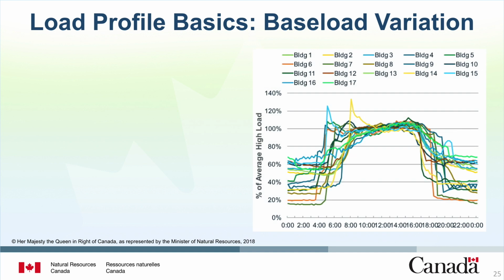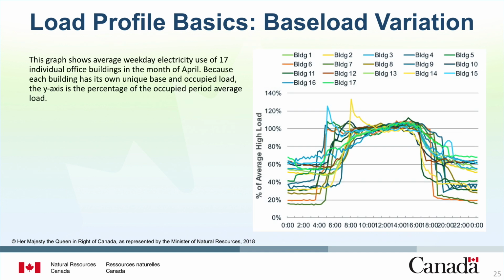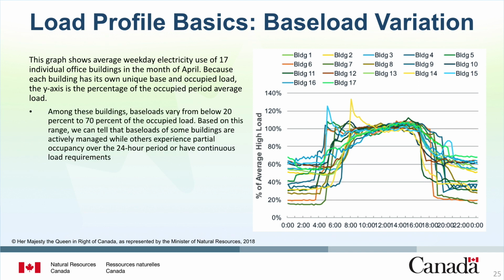We can also learn from load profiles that base loads can vary widely from building to building. This graph shows average weekday electricity use of 17 individual office buildings in the month of April. Because each building has its own unique base and occupied load, the y-axis is the percentage of the occupied period average load. For example, at 2 a.m., Building 6 uses 20% of its average occupied load. Among these buildings, base loads vary from below 20% to 70% of the occupied load.